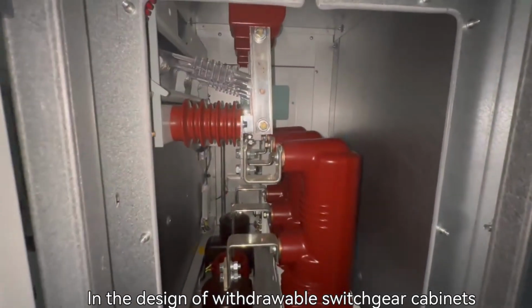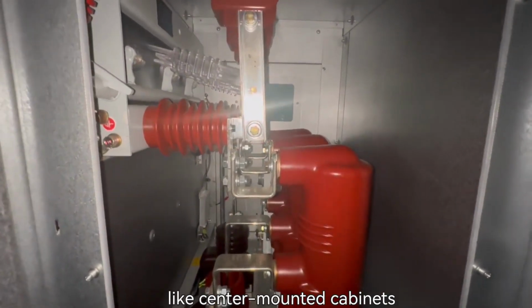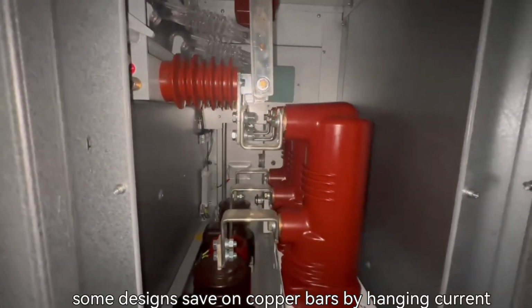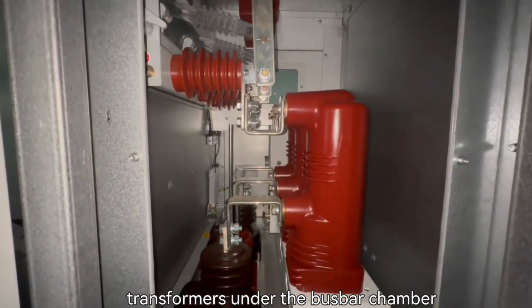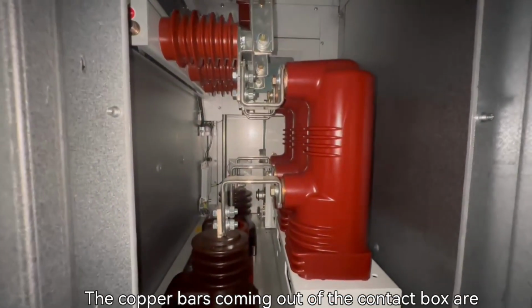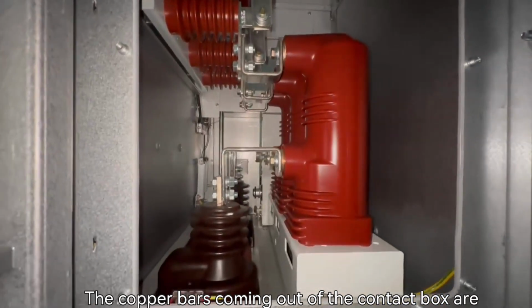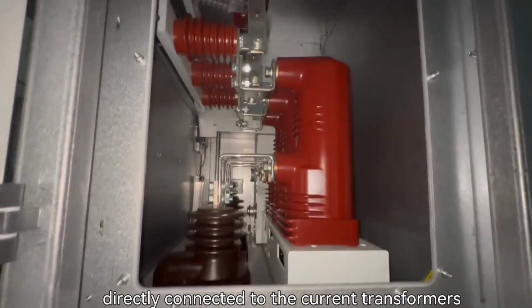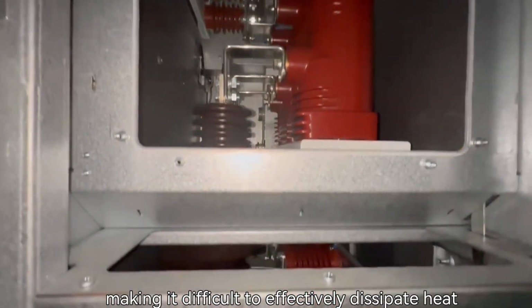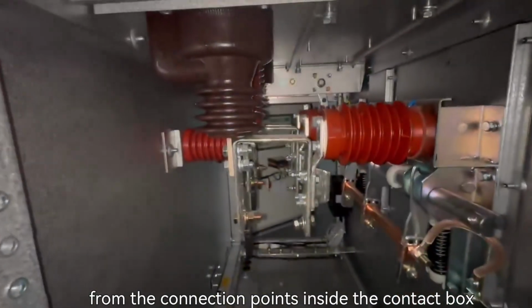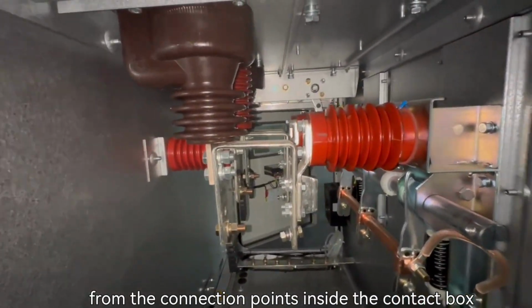In the design of withdrawable switchgear cabinets like center-mounted cabinets, some designs save on copper bars by hanging current transformers under the bus bar chamber. The copper bars coming out of the contact box are directly connected to the current transformers, making it difficult to effectively dissipate heat from the connection points inside the contact box.